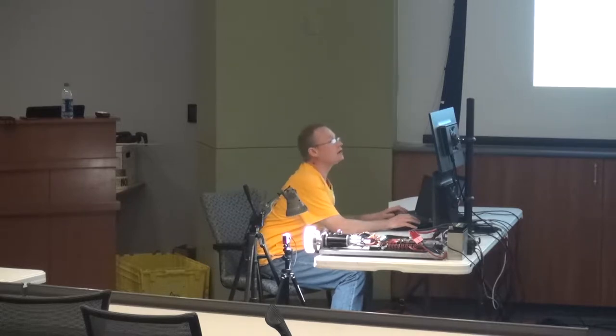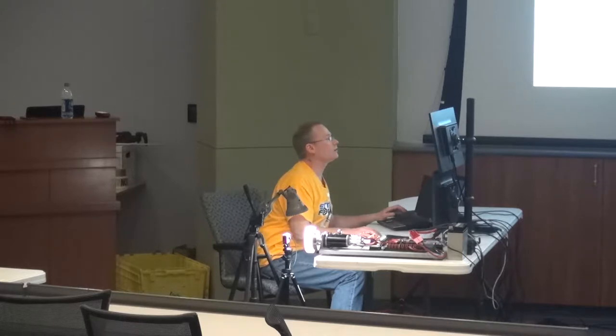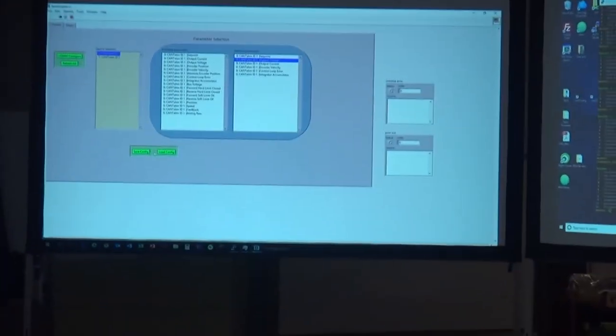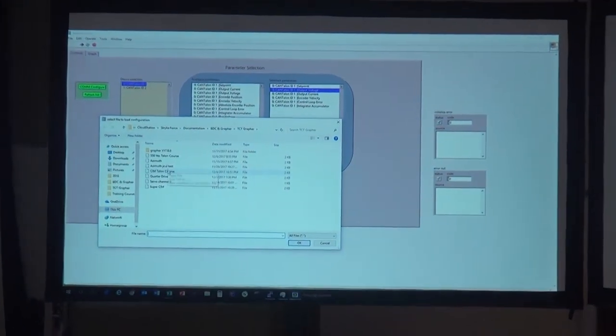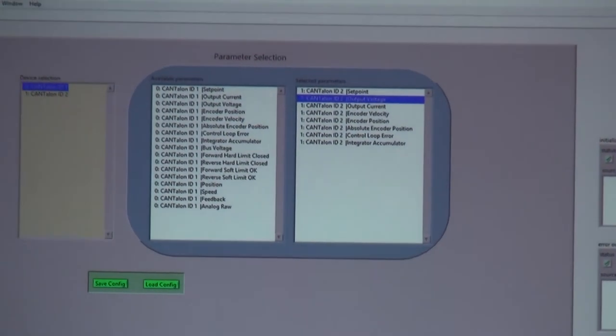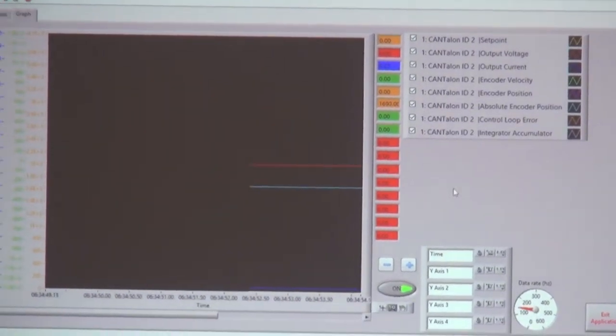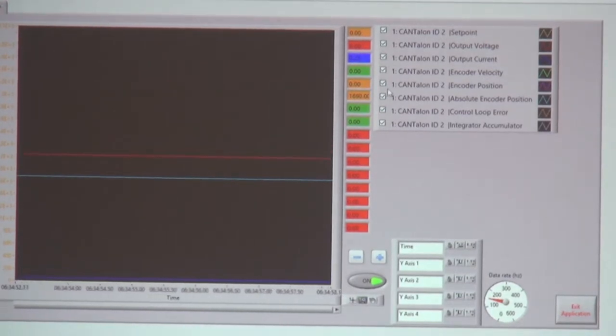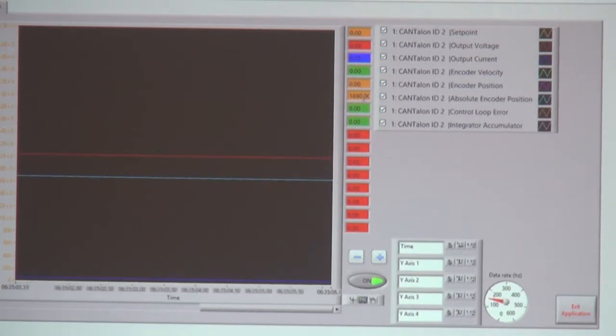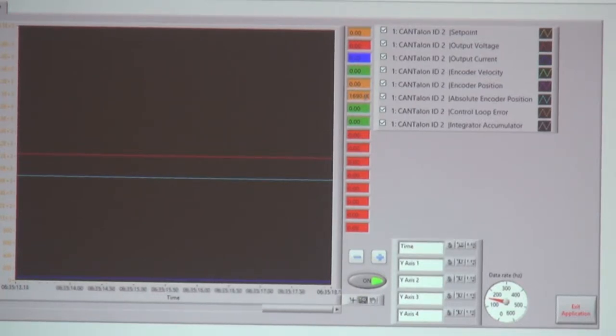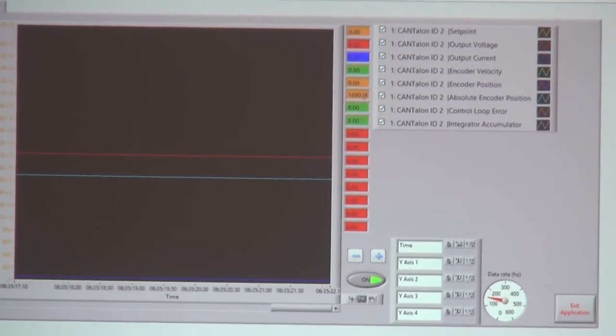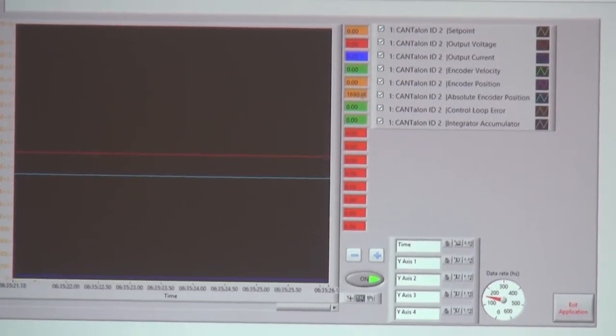Now let's fire this back up and go back over here. When I look at my incremental encoder, I have zeroed it. My absolute encoder I can't zero — it's absolute. It's telling me wherever it's at, and right now from zero to 4096, it is sitting at 1690. 1690 happens to be my spot straight up.